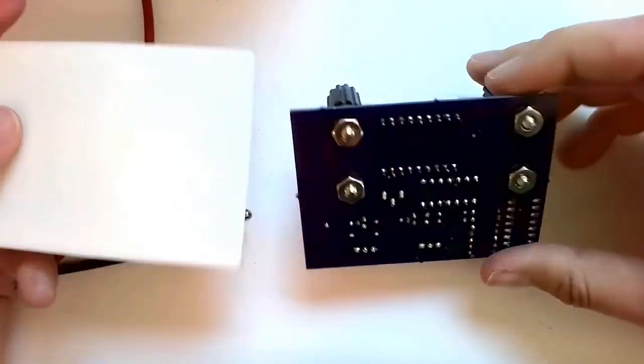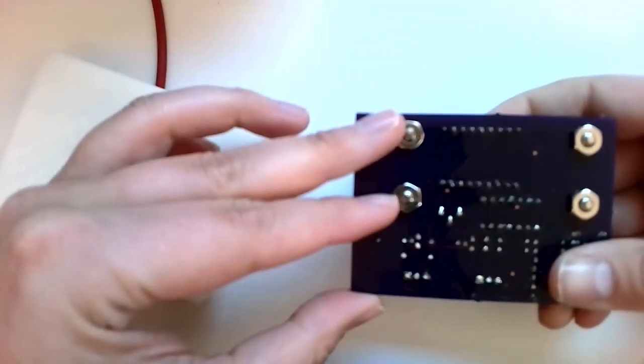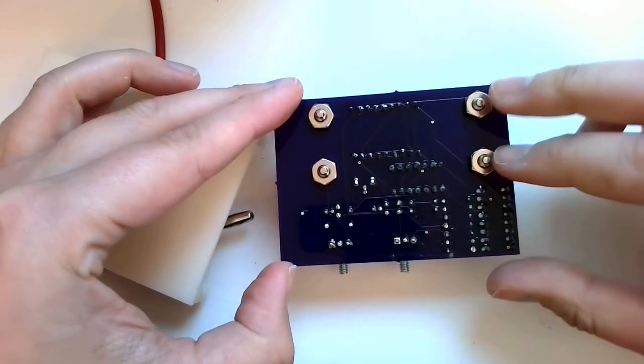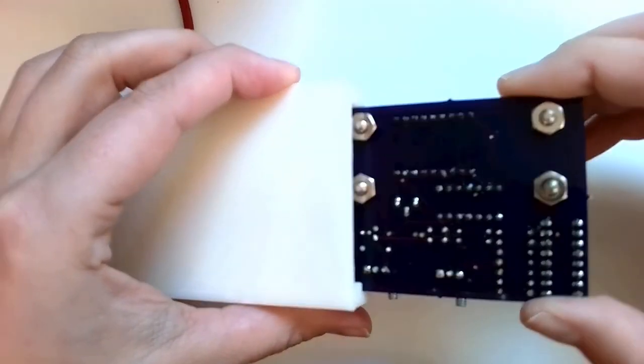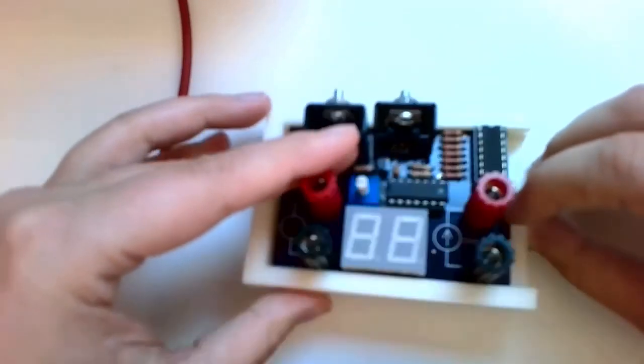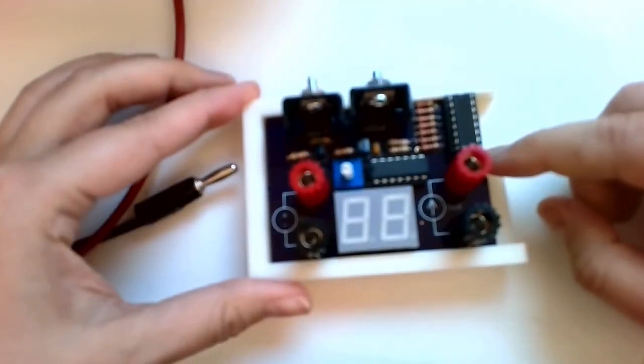Because we have up to 20 volts or so applied on this side, and we have a constant current coming out of this side. It's going to be important to make sure that they stay seated in the insulator backing.